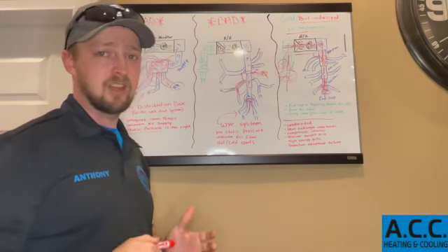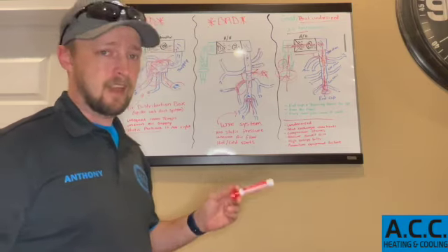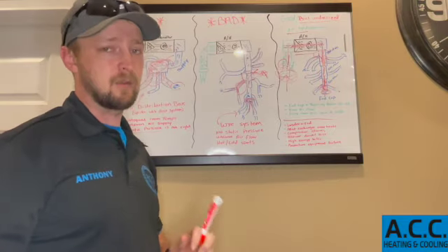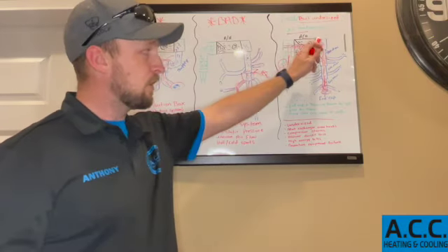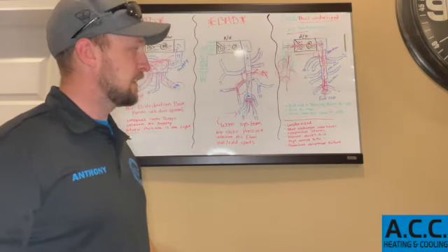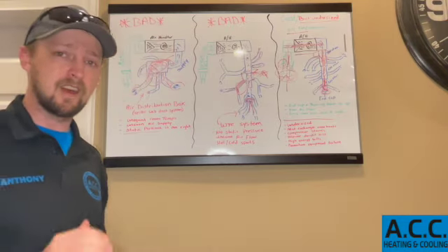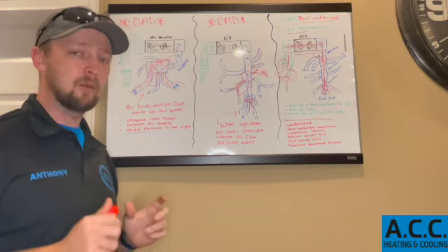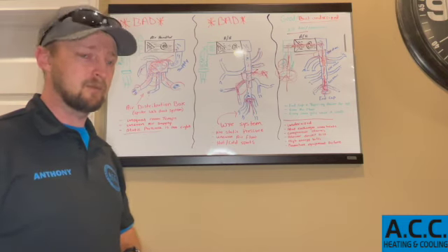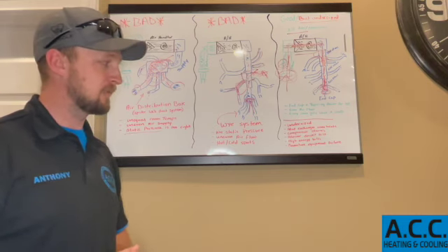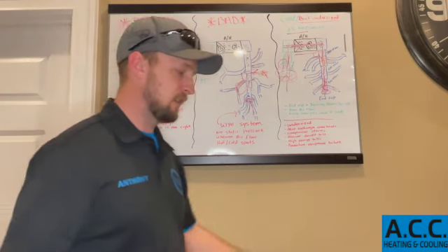You know, things change all the time. And if your house is 20, 25 years old, I can pretty much guarantee you I can walk in your crawl space or go up in your attic and your return is too small or your supply is too small. This is something big that people need to start paying more attention to. If you need to replace your system, you need to ask that technician, why? What made that system fail? And if he says, I don't know, the compressor just went out, that's why the system quit working, tell him to look at the ductwork. Tell him to check the airflow.